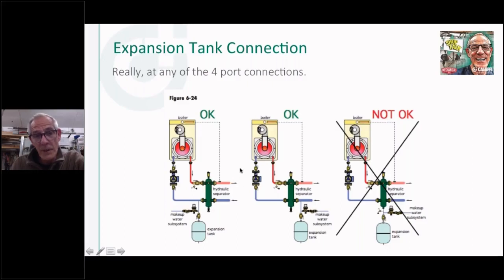You say, well, what happens to the pumps that I start putting distribution pumps, maybe one, maybe two, maybe they're variable speed? Well, because this is that wide open, low velocity, low pressure drop zone, this point of no pressure change is established through this chamber, and whatever pump I would put up here on the outlet side, on the distribution side of the circulator, references this point right here as its point of no pressure change. So this becomes a point of no pressure change for this pump, whatever pumps I add on to it. So that's a good spot. It could be on this side. Really, any one of the four ports could be the expansion tank connection.